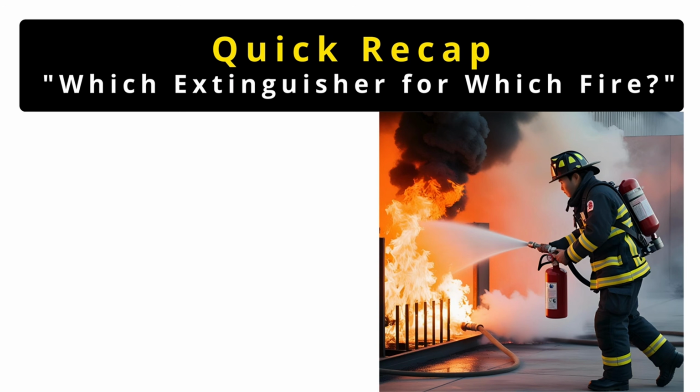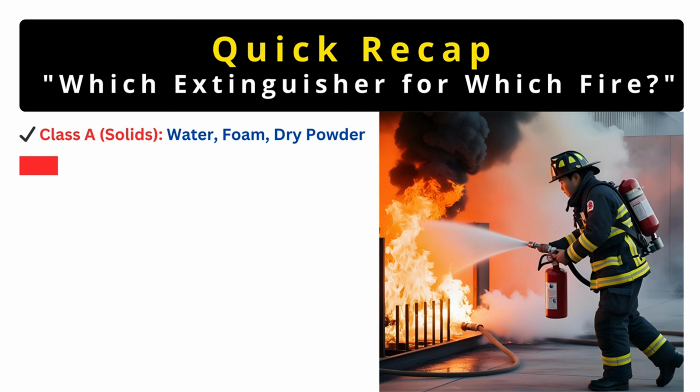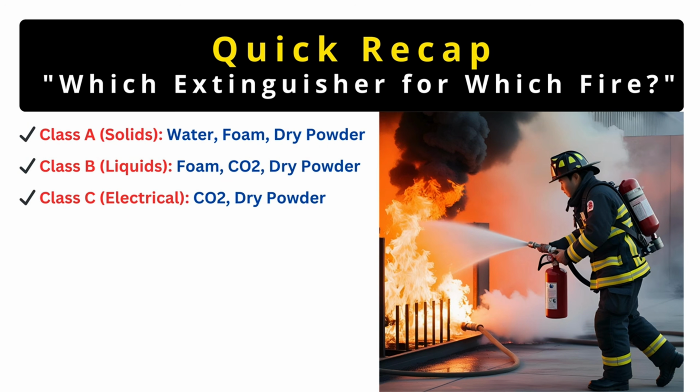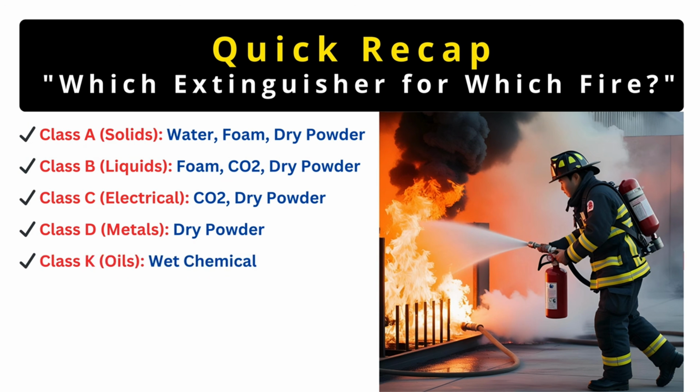Let's do a quick recap. For ordinary fires like wood or paper, use water or foam. For flammable liquids, foam or CO2. Electrical fires, CO2 or dry powder. Metal fires, only dry powder. And for kitchen fires, wet chemical is your best friend.